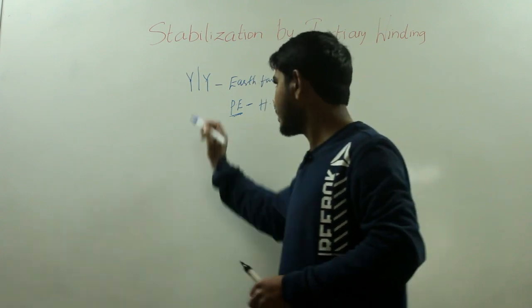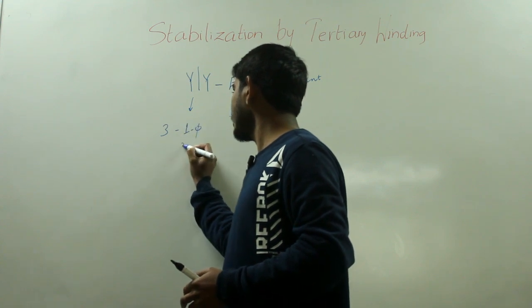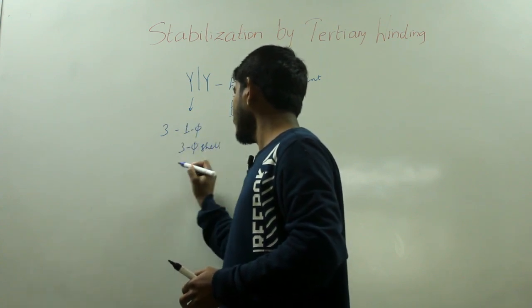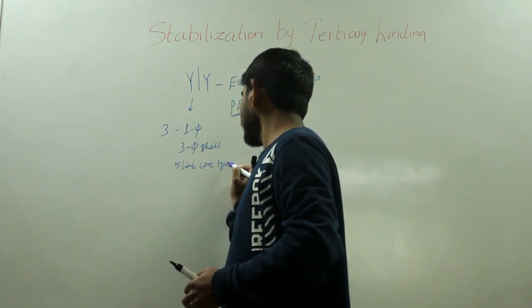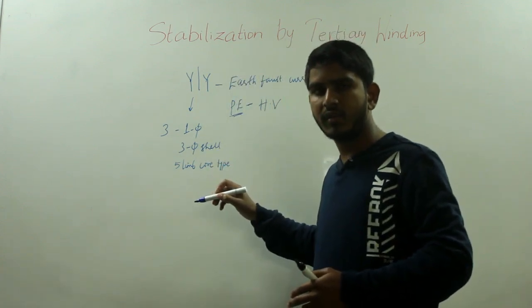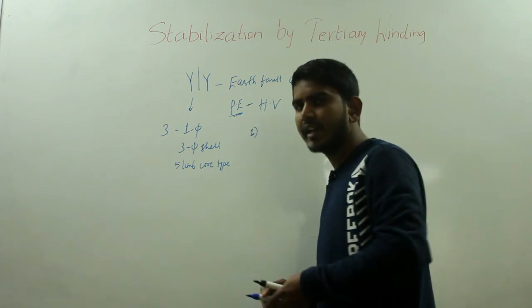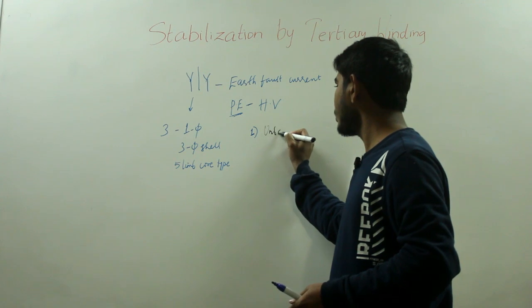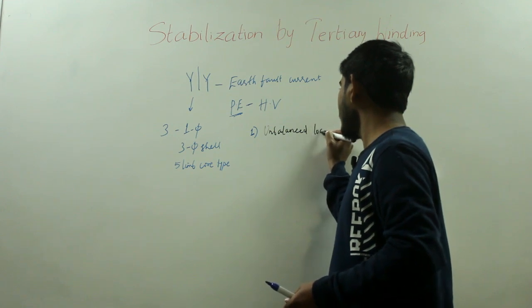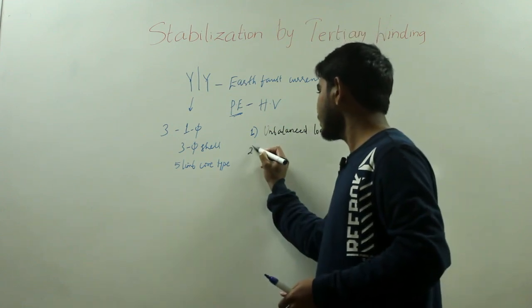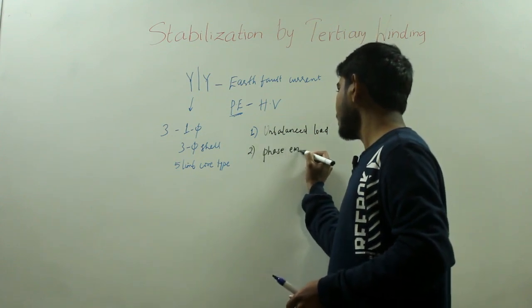If I talk about the star-star connected transformer comprising three single-phase units, a three-phase shell unit, or a five-limb core type transformer, these transformers have two drawbacks when operated under unbalanced load. The first drawback is that they cannot readily supply an unbalanced load between line and neutral, and the second drawback is that their phase EMF may get distorted due to harmonic EMFs.